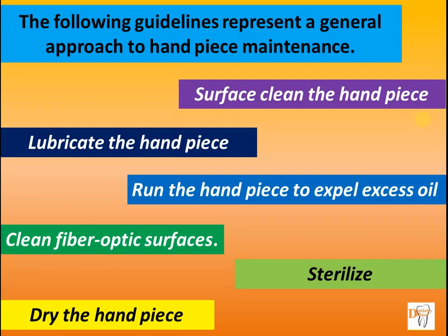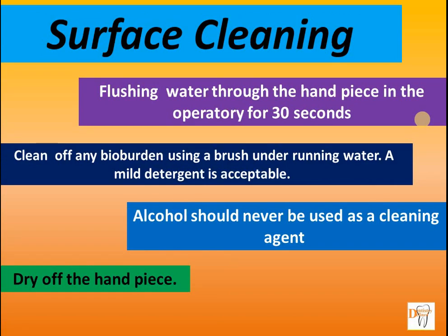So the following guidelines represent the general approach to maintenance of the handpiece: surface cleaning, lubrication, running the handpiece after lubrication to expel excess oil, cleaning fiber optic surfaces, sterilization and drying the handpiece. Coming on to surface cleaning.